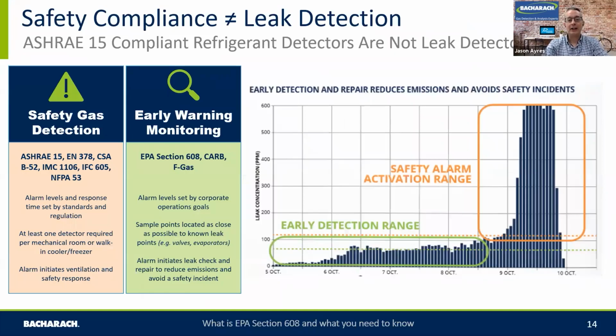And that does really lead into the definition of gas detection. There are two ways of looking at gas detection: safety compliance and leak detection. I just want to spend a short while clarifying the difference, because it's extremely important if you're looking at a detection system to help you reduce your refrigerant usage, be ahead of the game, and look at EPA 608 compliance. First of all, we have safety gas detection, ASHRAE 15, EN 378 in Europe.